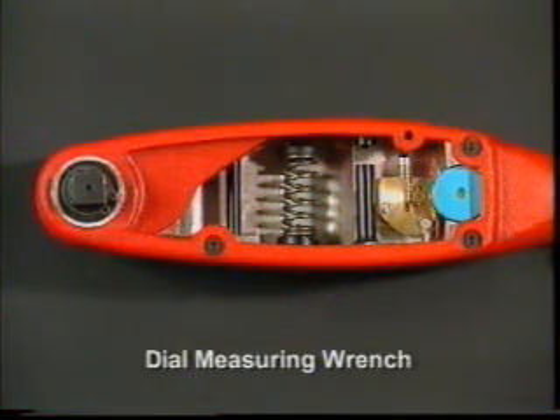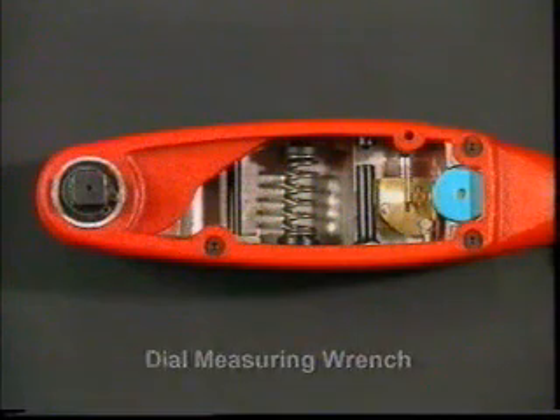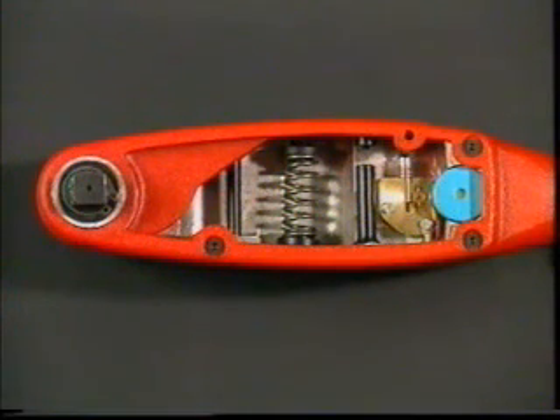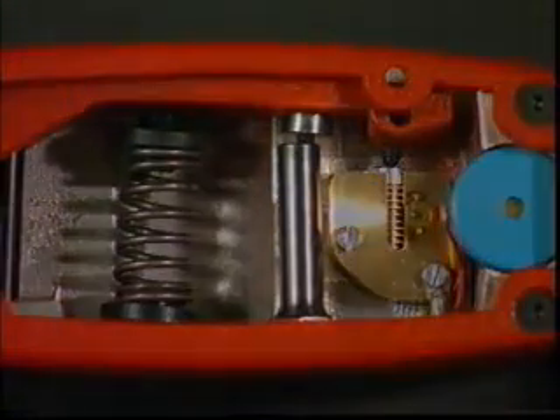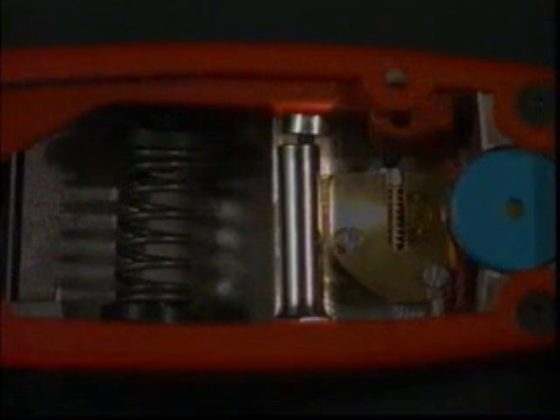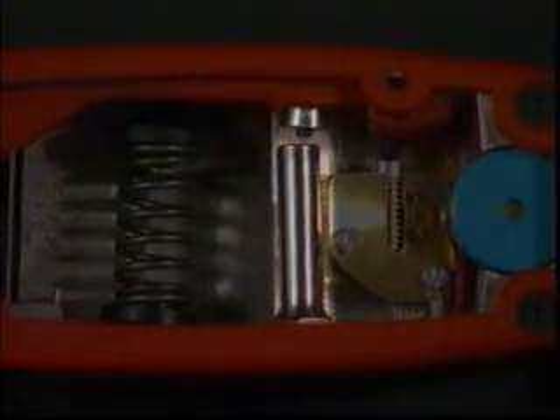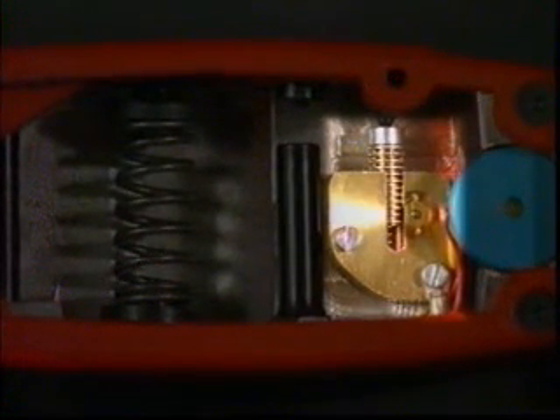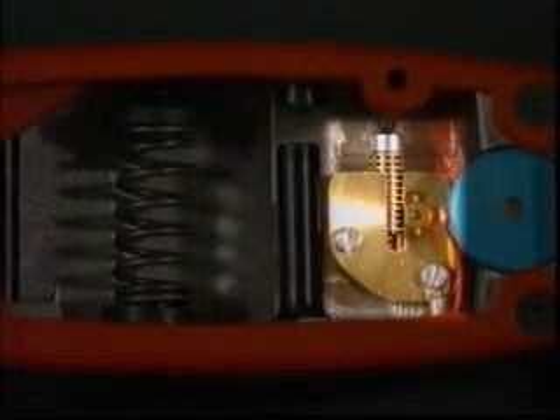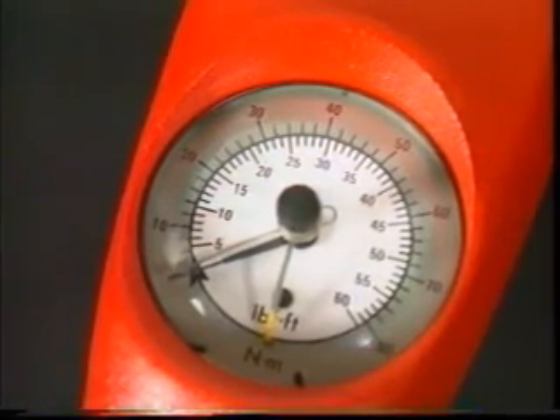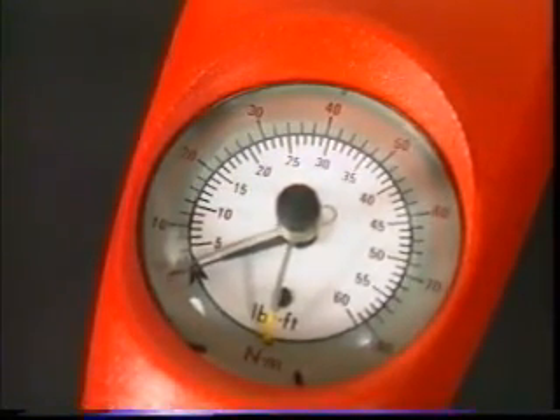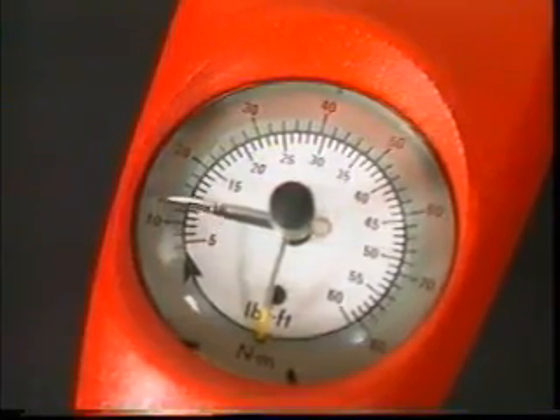The Torqueleader dial measuring wrench is one of several tools commonly found in research and development departments for accurately measuring and applying torque. The wrench uses a finely tuned spring mounted between the two pivoting sections of the tool. As torque is applied, the spring compresses, and an overload protection stop prevents the user from damaging the mechanism by applying excessive force. The amount of movement is measured through a sturdy rack and pinion system, accurately converting linear motion into a reading on the dial of the wrench.